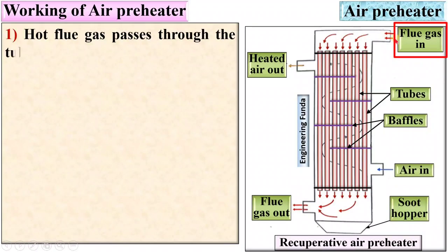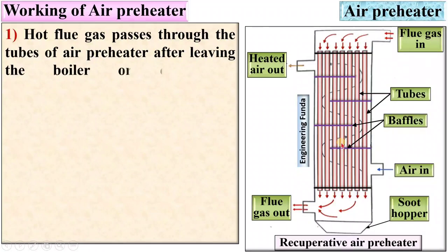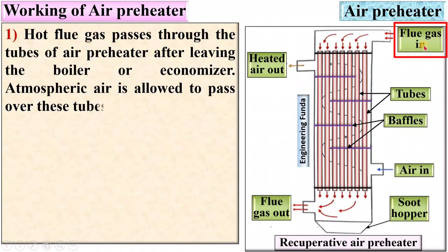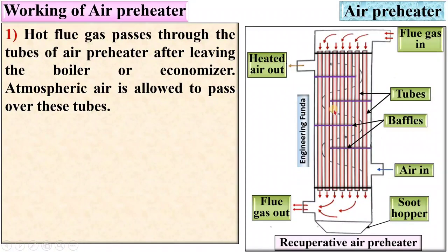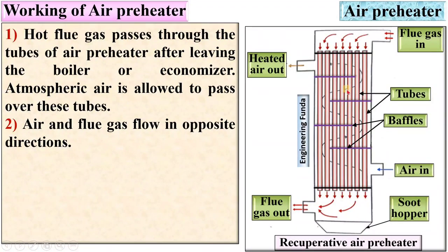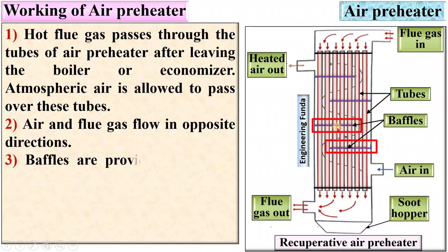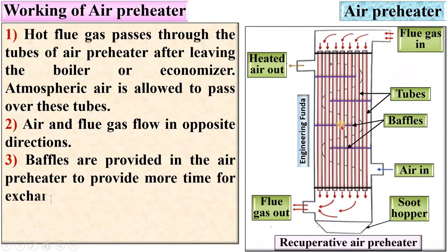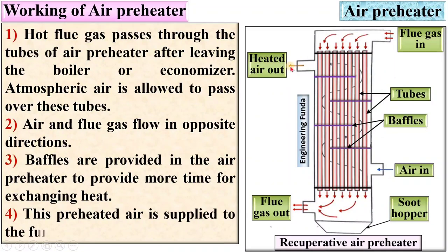Working of air preheater: flue gases pass through the tubes of the air preheater after leaving the boiler or economizer. Atmospheric air is allowed to pass over these tubes. Air and flue gases flow in opposite directions — flue gas flows in the downward direction whereas air flows in the upward direction, which is sometimes called counter flow. Baffles are provided to allow more time for exchanging heat. This preheated air is then supplied to the furnace of the boiler.